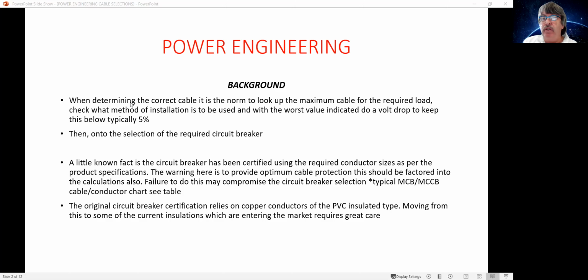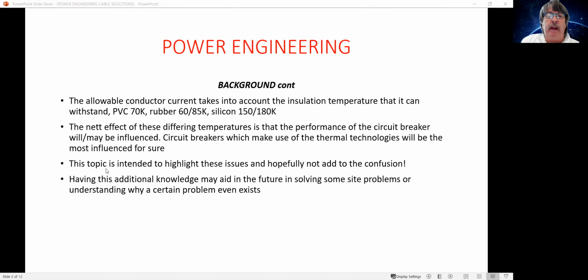So generally speaking, the circuit breaker, as we said, has been certified using some copper conductive material, and it's generally indicated with a PVC insulation, that being the most popular for many, many years. And moving from any of the current types of insulation would require quite a bit of care. So if we're using PVC and copper, generally we are in the standard that has been applied during the tests to the circuit breakers. The allowable conductor is obviously protected by the circuit breaker. That's its whole and primary function, really.